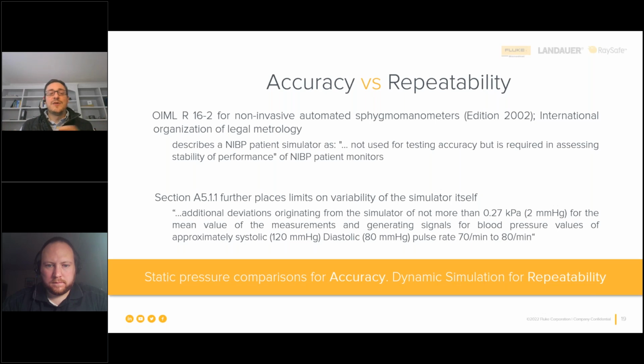So there's a mix between qualitative and quantitative analysis here, but it is assumed that if the NIBP measured and displayed on the patient monitor matches the pulse rate, systolic, diastolic, and MAP numerics, if these all fall within the accuracy range specified by the patient monitor, then the performance has to be acceptable.